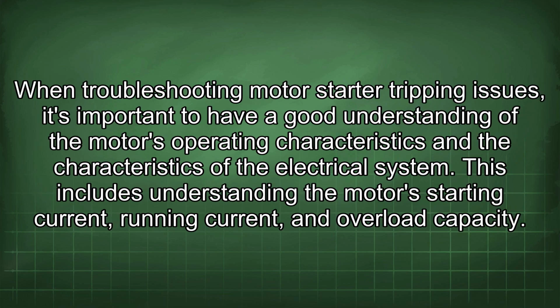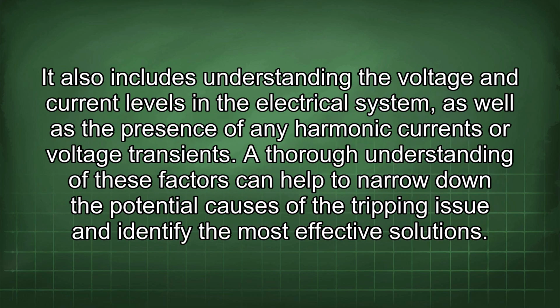When troubleshooting motor starter tripping issues, it's important to have a good understanding of the motor's operating characteristics and the characteristics of the electrical system. This includes understanding the motor's starting current, running current, and overload capacity. It also includes understanding the voltage and current levels in the electrical system, as well as the presence of any harmonic currents or voltage transients.